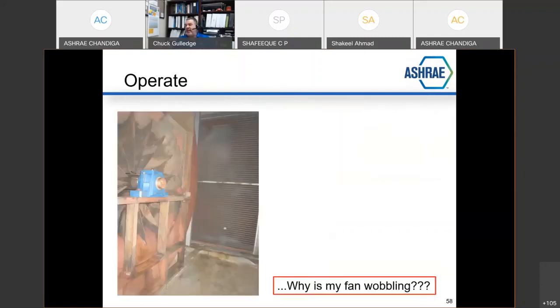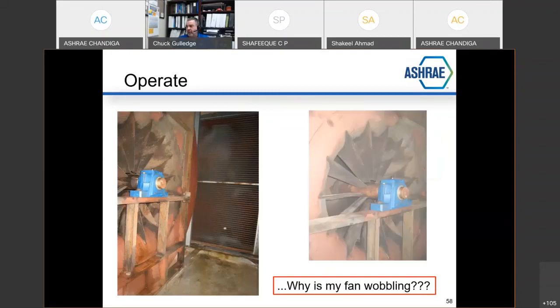Why is my fan wobbling? That is a fan. That is dirt. That is grime. They obviously had a problem with the fan wobbling associated with the fan wheel being dirty and out of balance. What was their solution? Let's just replace the bearing that got damaged and not deal with the source problem of a wobbling fan and shaft. Pretty good solution. It's going to be temporary.